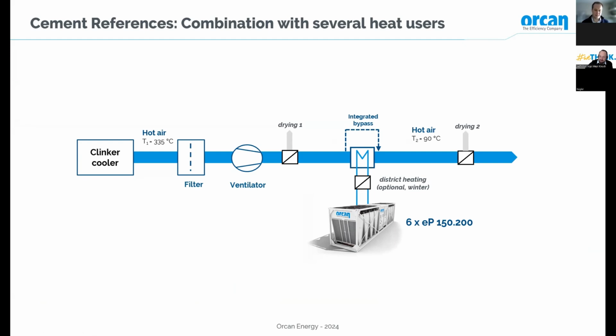Most heat-to-heat uses are already done because there was always a good business case. The problem is that the heat user is a lot of times not synchronized with the heat producer. For example, with district heating on smaller heating grids, you only have 2,000-3,000 hours of operation, and you have to pay back a quite complex and big installation with that.